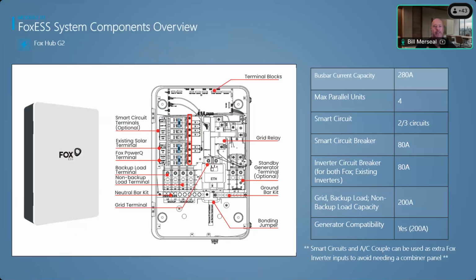So if you don't have the 2-wire start stop, we can just verify, hey, as soon as power goes into that relay, it's going to flip the grid relay to the off position, and that will prioritize the power going to that home load. So the generator, depending on the type of generator, we've got to be a little careful on that because if you have a generator that you're trying to run the whole home load and it's not a whole home generator, we need to break that out a little bit because you might overload that generator and that generator will just stall out.